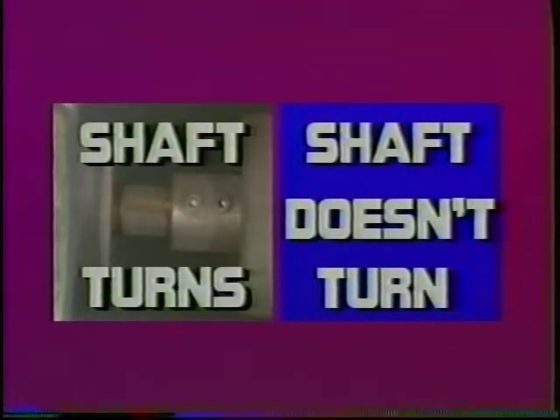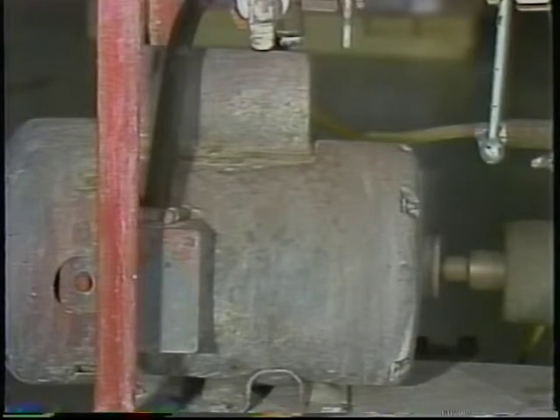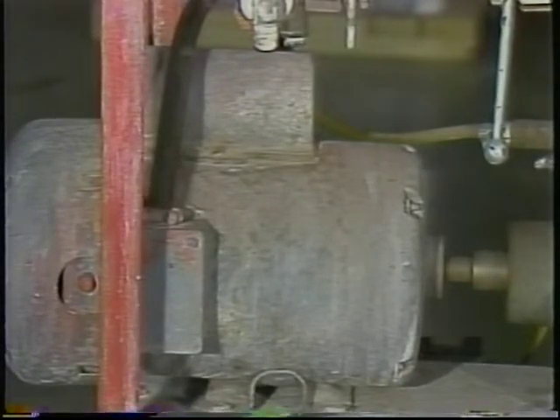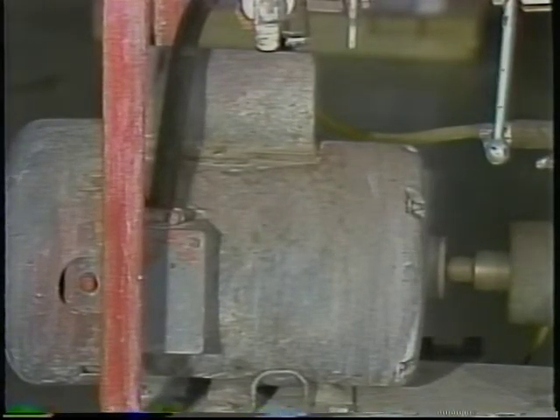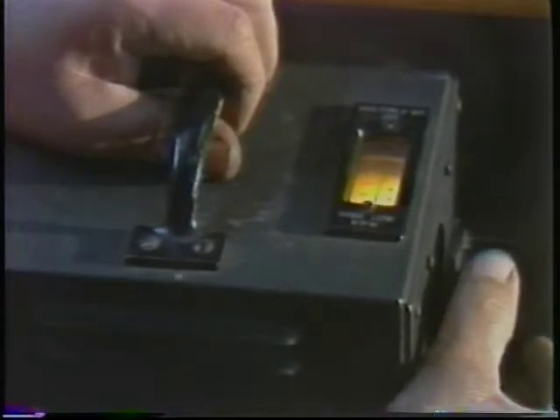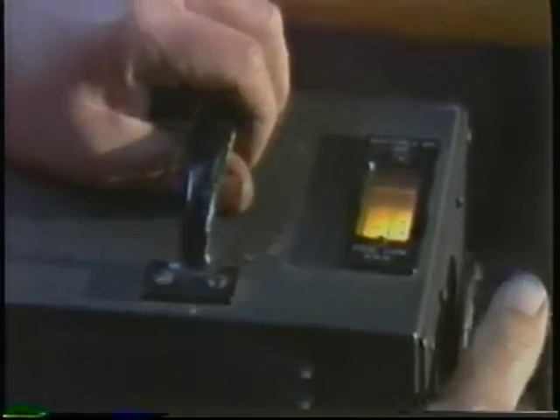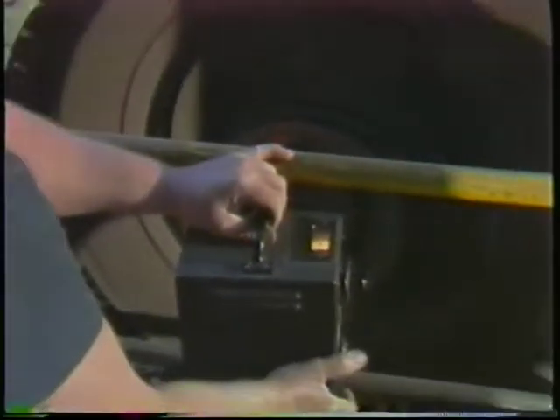Suppose the motor does start up. If it is a single-phase capacitor start motor, you know that the start winding, the centrifugal switch, and the capacitor are probably okay if the motor comes up to normal speed. You can also rule out the rotor excitation circuits of a synchronous motor if the motor pulls into synchronous speed. On the other hand, if it does not pull into synchronous speed, suspect the rotor excitation circuit.